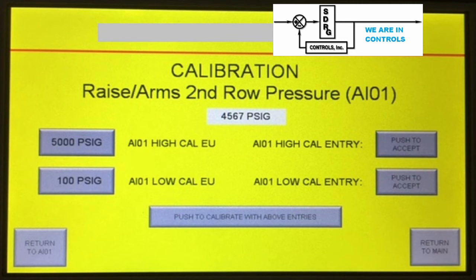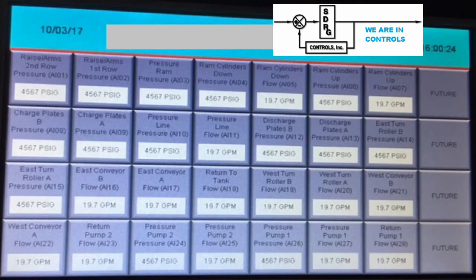Once we decided on using the HMI for displaying the system, the next thing considered was how to calibrate all 28 different pressure transmitters for their various locations. The decision was to make a calibration screen on the HMI so each one can be calibrated individually, and that's what was done.